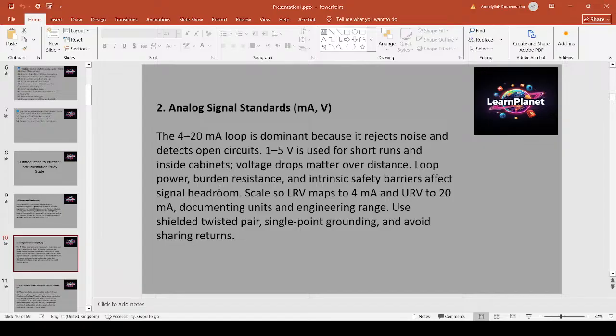Loop power, burden resistance, and intrinsically safe barriers affect signal headroom. Scale so LRV maps to 4 milliamps and URV to 20 milliamps. Document units and engineering range. Use shielded twisted pair, single point to point, single point grounding, and avoid shared returns.